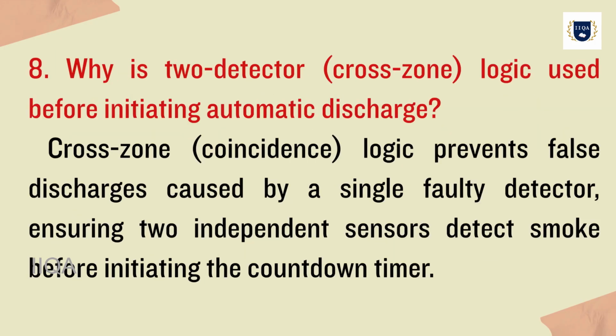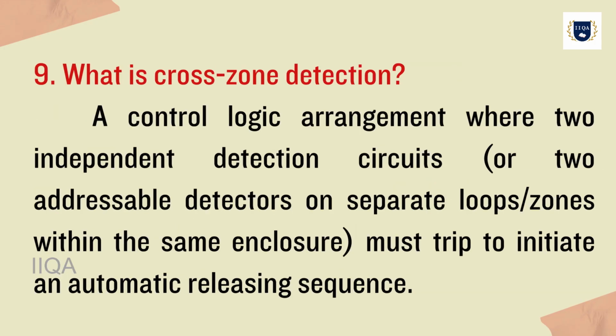8. Why is detector cross-zone logic used before initiating automatic discharge? Cross-zone coincidence logic prevents false discharges caused by a single faulty detector, ensuring two independent sensors detect smoke before initiating the countdown timer. 9. What is cross-zone detection? A control logic arrangement where two independent detection circuits, or two addressable detectors on separate loops or zones within the same enclosure, must trip to initiate an automatic releasing sequence.